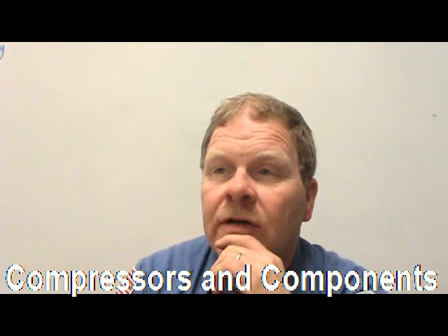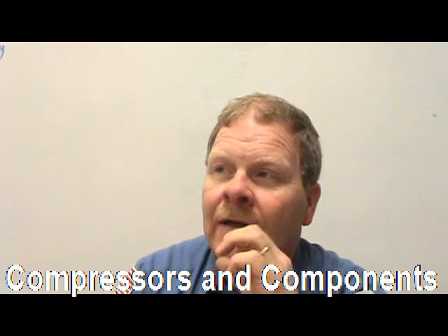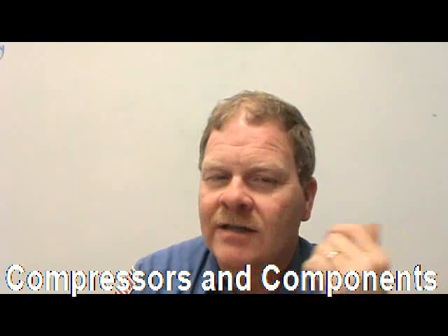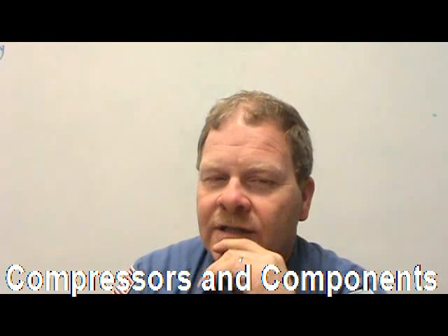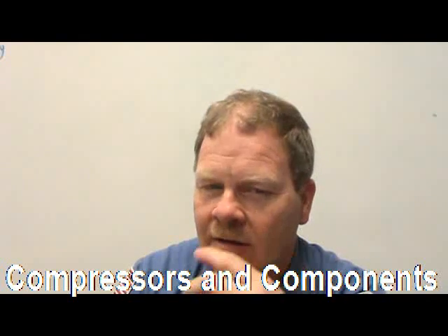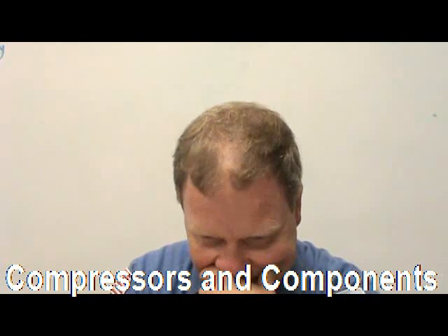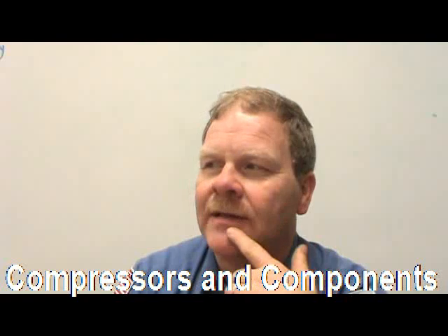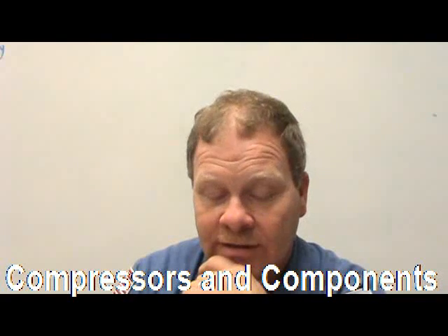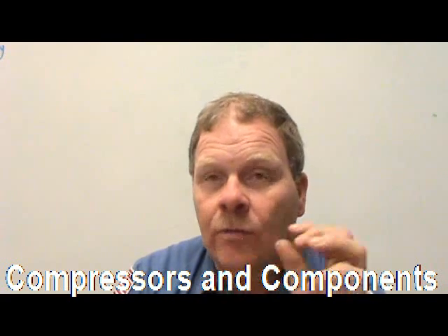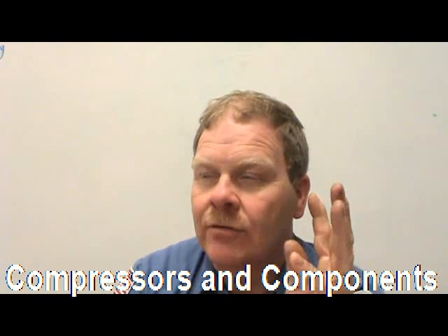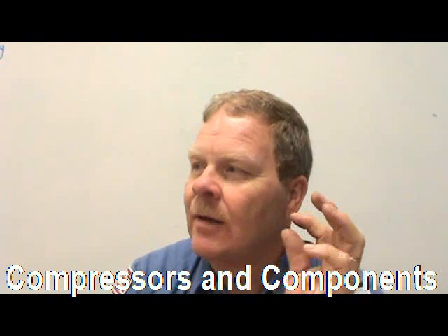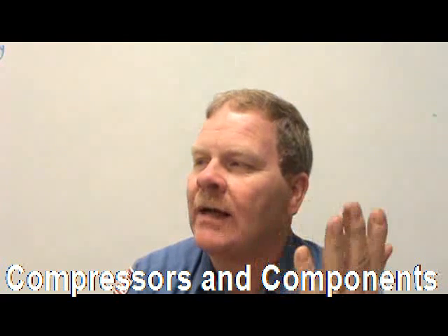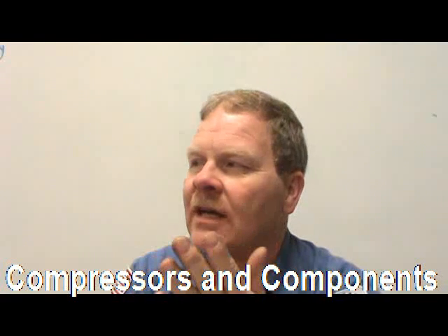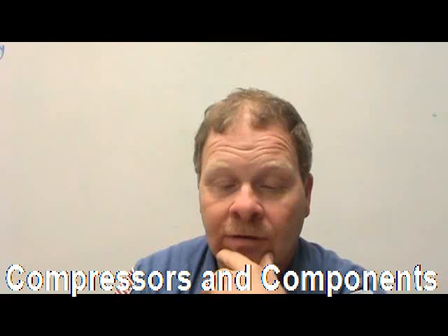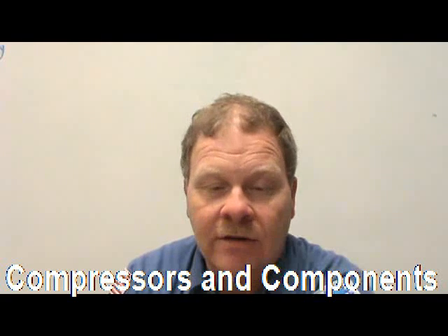They also have filters you can put in the suction port on the compressor. I've got some in there, little screens you can press in, so anything trying to come out of the system and go into the compressor gets caught in that screen. Those screens cost about $5 or $6 apiece, and I can show you all those things. It's pretty cool stuff. You've got 3 different size screens, and sometimes you're basically putting it not in the compressor, but in the low side, in the suction line port where it hooks to the compressor.